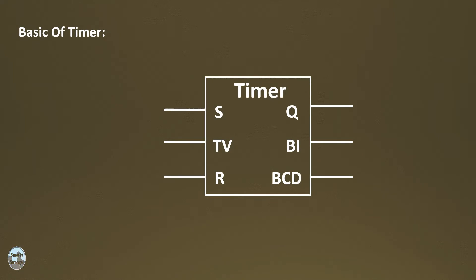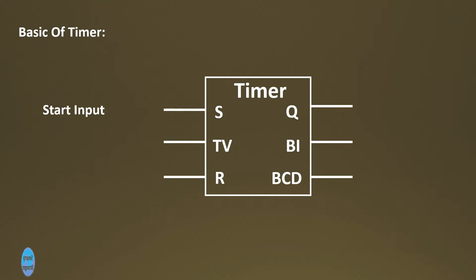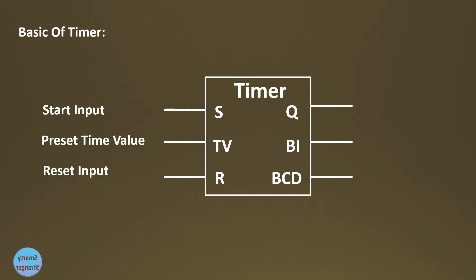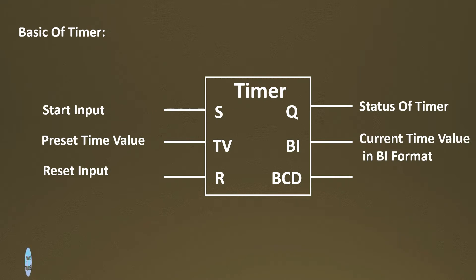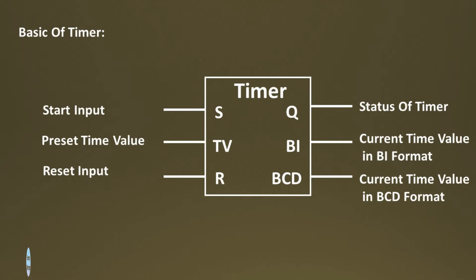All PLC softwares normally have the same shape of timer, though pins of inputs and outputs may differ — you can take help from its manual. The S pin is used to start or trigger the timer instruction. The TV pin is used to set the preset time value. The R pin is used to reset the timer instruction. The Q pin shows the status of the timer instruction. The BI pin shows the current value in BI format, and the BCD pin shows the current value in BCD format.